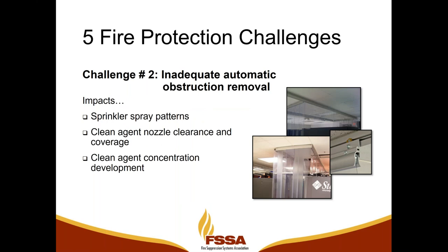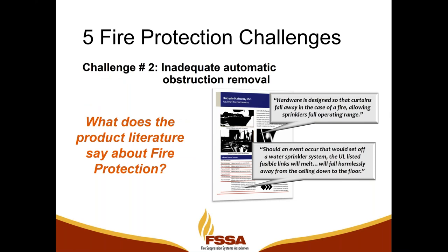Challenge two is inadequate obstruction removal. Understand that many of these obstructions or partitions for aisle containment are intended to automatically remove themselves. If they are not removed adequately, they can impact the sprinkler spray patterns, the clean agent nozzle clearances, and the concentration development. One of the early challenges that aisle containment posed to fire protection, and lots of data centers still exist like this today, was the plastic strip curtains used for containment. They were installed on aluminum rails, and those rails were attached to the ceiling grid using thermal fusible links. On the slide you can read some of this language, which ultimately came from some manufacturers' literature, but their names have been removed to protect the guilty.